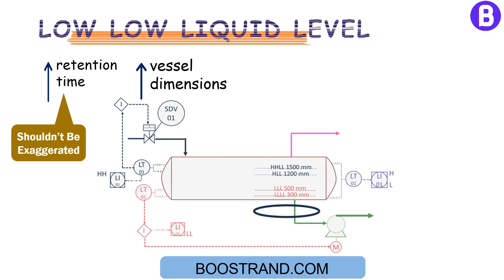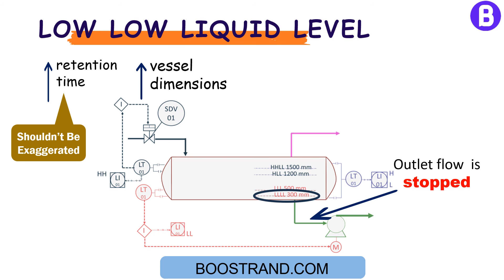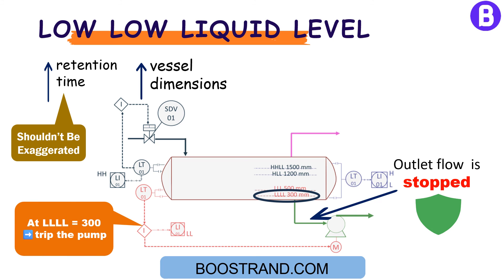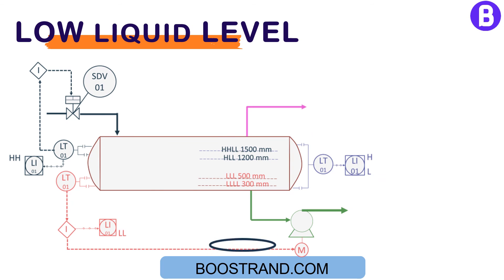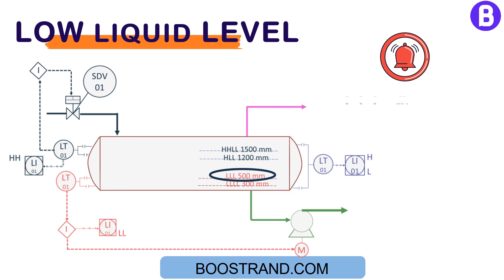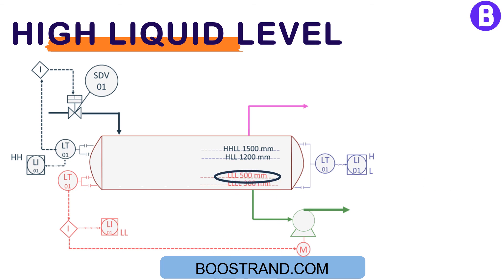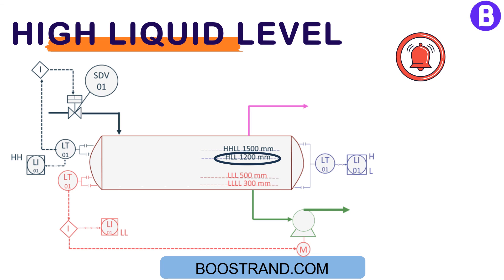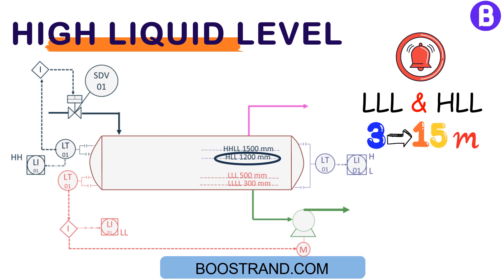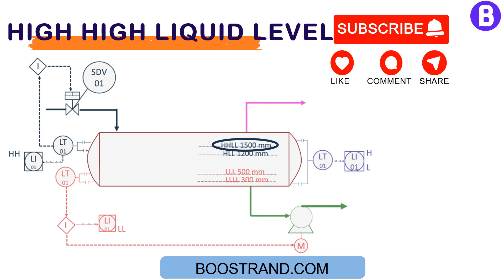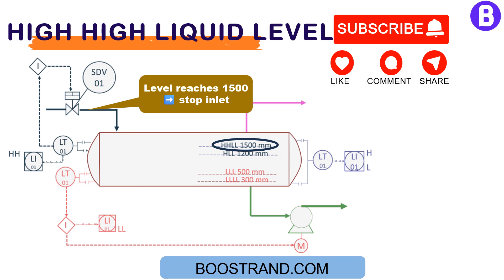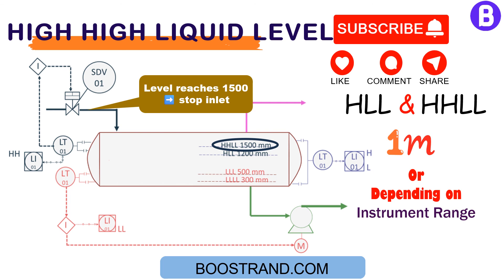The retention times are used to size and obtain the liquid levels: low low level, where the outlet flow from the vessel would be stopped — usually linked with safety interlocks to stop the pump or close the shutdown valve; low level, where the operator would receive an alarm; the usual timing between low level and low low level is one minute or depending on the instrument range, whichever is greater; high liquid level, where the operator would receive an alarm — the usual timing between low level and high level is 3 to 15 minutes depending on the criticality of the service; and high high level, where the inlet flow to the vessel shall be stopped, with the usual timing between high level and high high level being one minute or depending on the instrument range, whichever is greater.